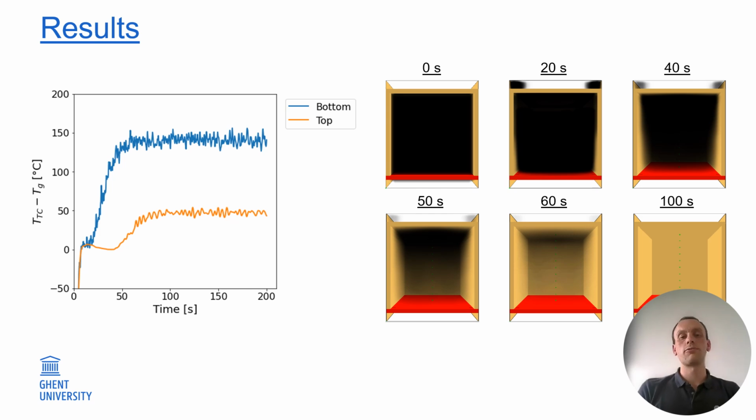What we want to demonstrate first is that as long as you're measuring with your thermocouple inside the smoke layer, that you're measuring the real gas temperature. So as soon as we start the simulation, due to buoyancy, the smoke flows out of the compartment and the smoke layer gradually moves upwards, which means that the zone close to the floor gets into an optically thin environment sooner than the zone near the top of the compartment where the smoke layer will be present a longer time.